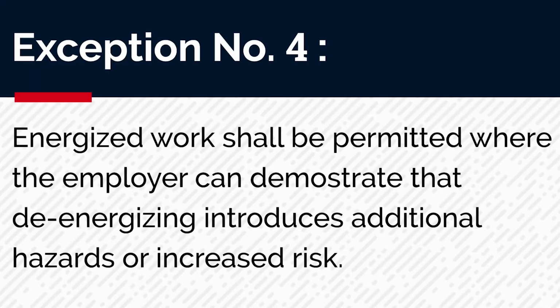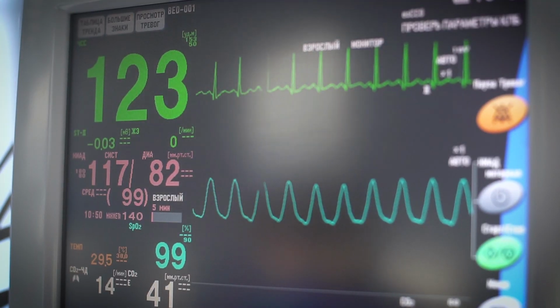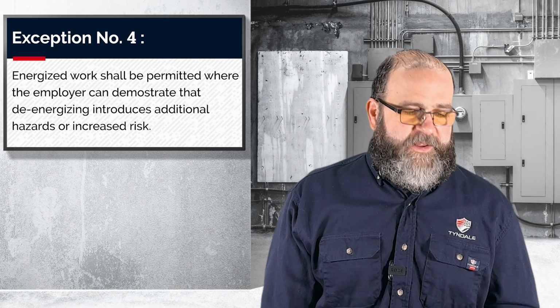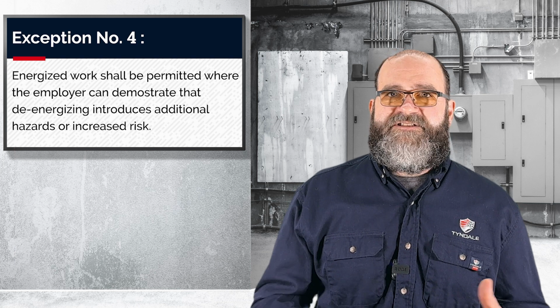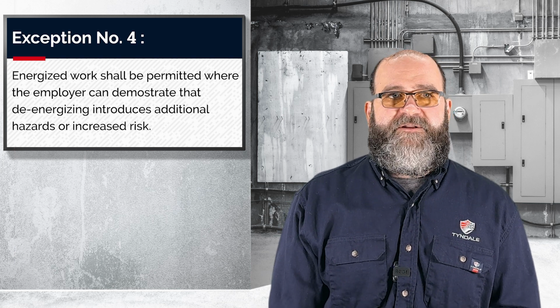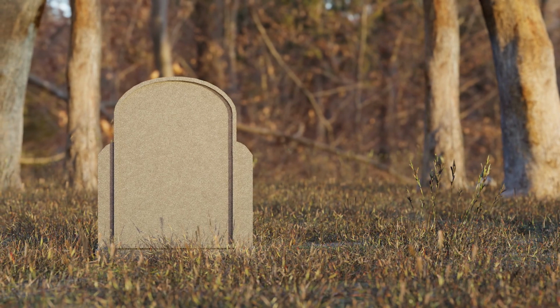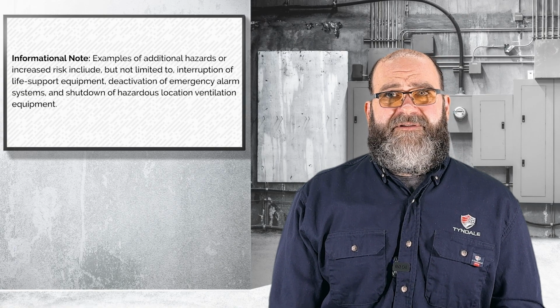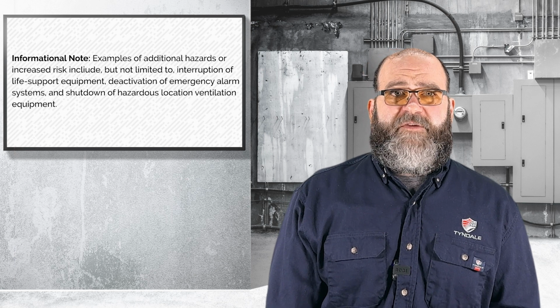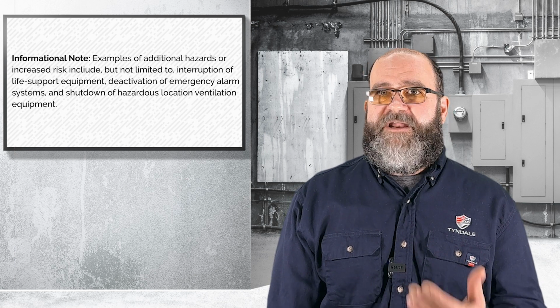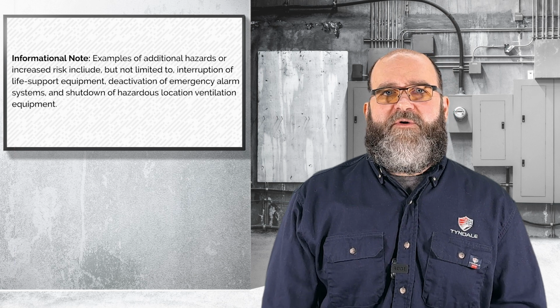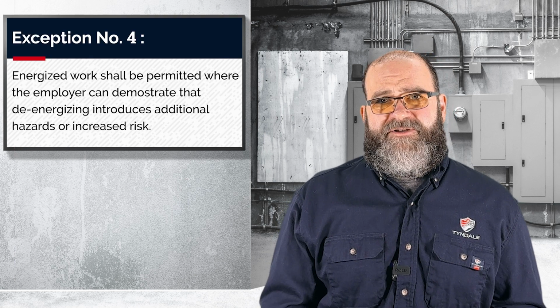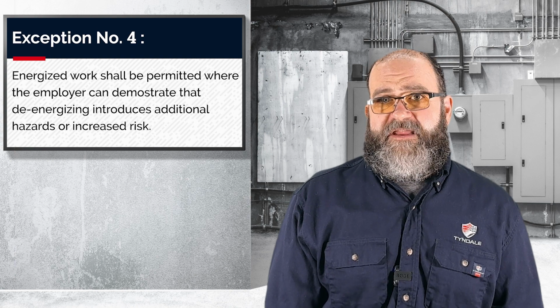Exception number 4 tells us that energized work shall be permitted where the employer can demonstrate that de-energizing introduces additional hazards or increased risk. Examples of this might be turning off life support, turning off toxic or flammable gas ventilation, or emergency alarms for that type of situation. Situations that will kill somebody. And just because you say it's infeasible doesn't mean that it is infeasible. You have to provide documentation of this, rationale, reasoning. People have to sign these forms. The bottom line is you can rarely justify energized work per the 70E and OSHA.